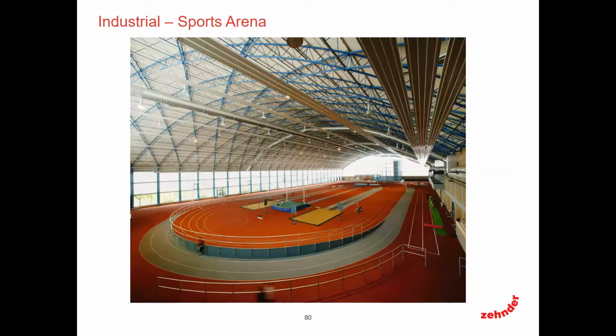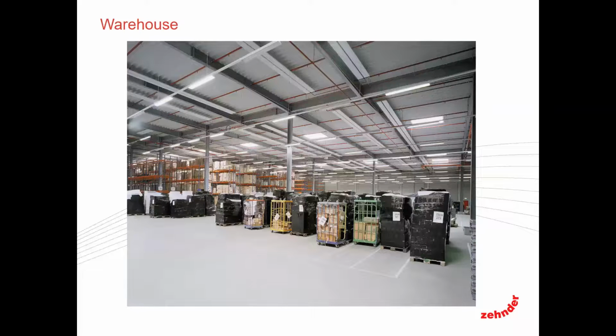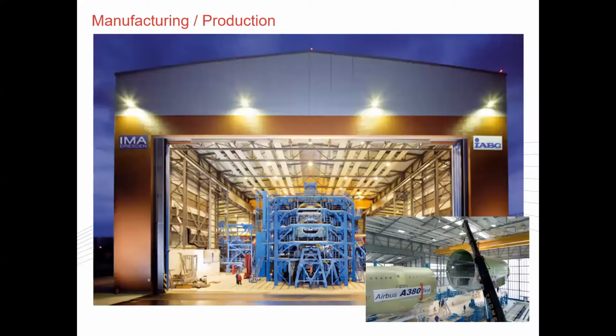A lot of sports arenas, things of this nature that we typically see, warehouses, applications like this, because it's a lower cost installation. For production facilities and manufacturing, if you are designing a manufacturing or commercial space that has waste heat, it's a great application to recover your waste heat through a water-to-water heat exchanger, or an air-to-water heat exchanger, and then utilize that water through the panels themselves. It's a great way to save some energy.